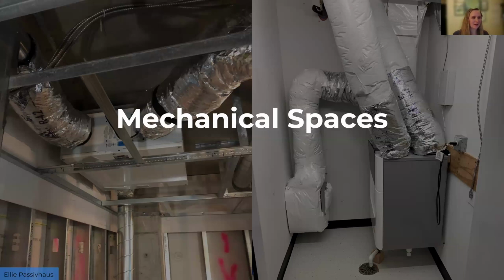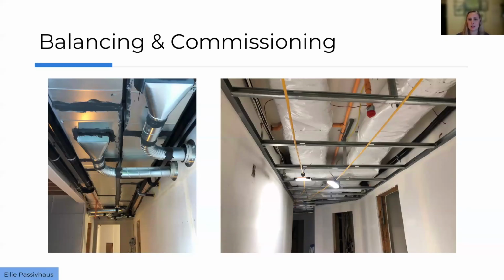A quick note about mechanical spaces. I include this for all of my HVAC mechanical folks. When using a horizontal or floor by floor balanced ventilation system, having enough space to install ductwork without jamming everything into a small closet is really, really critical. So especially for those on the design side of things, designing for space for those important systems, especially balanced ventilation, and getting buy-in and input from your mechanical teams early on is really important. In terms of balancing and commissioning, again, in my experience, smaller systems are a bit simpler to accurately balance or do sample verification of, but that's just going to be project to project dependent.